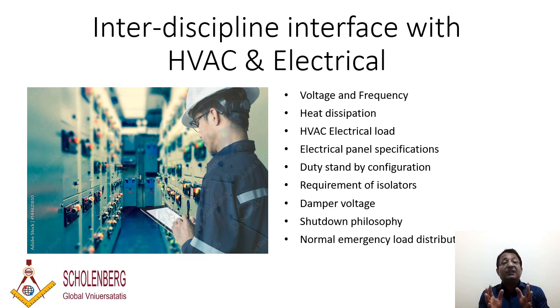Then you need to design the shutdown philosophy, because suppose something happens on the platform - suppose gas is detected or fire is detected, then how your control panel or HVAC panel will get closed. That kind of philosophy you need to sit together with technical safety discipline, electrical discipline, instrument discipline, all major disciplines. They have to sit and design the entire system shutdown philosophy.